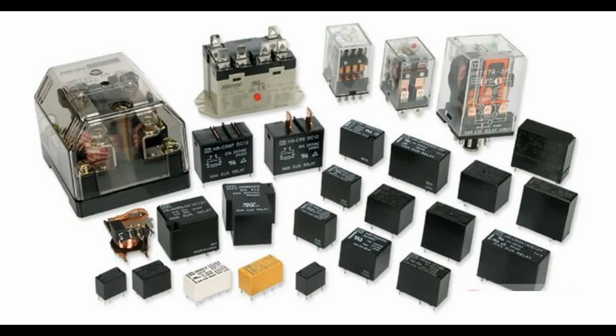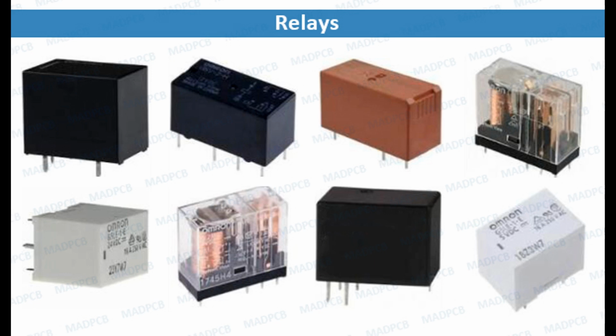Key characteristics. Memory function. Retains its last state even after the control power is removed, making it useful in applications where maintaining the relay state during power outages is important. Energy efficiency. Requires only a short pulse of power to change states, which minimizes power consumption. Durability. The latching mechanism reduces the need for constant power, resulting in less wear and tear on the relay components.